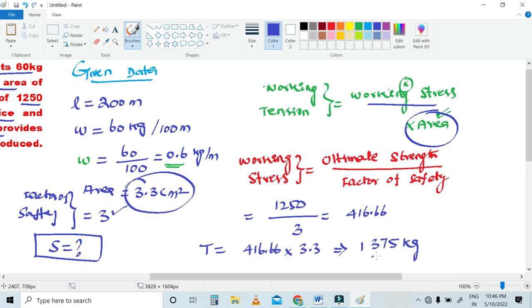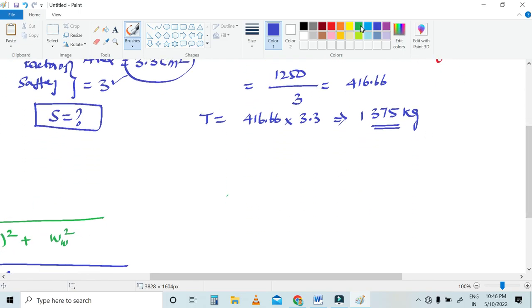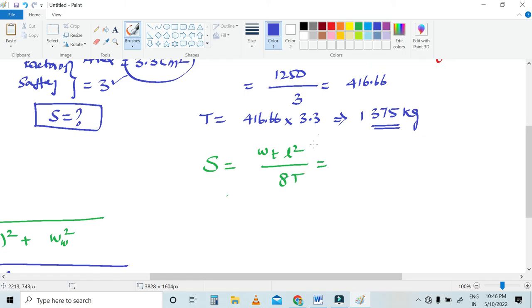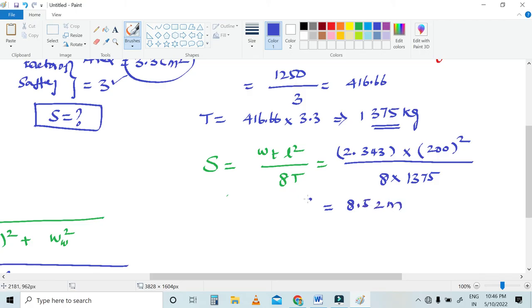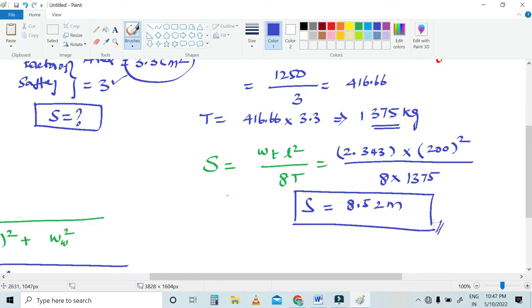Now calculate the sag. The formula is S equals Wt times L squared divided by 8 times T. Substituting: Wt is 2.343, L is 200 meters, and T is 1375 kg. So S equals 2.343 into 200 squared divided by 8 into 1375. The answer is 8.52 meters.